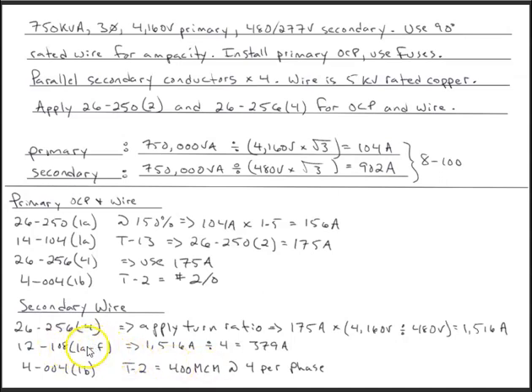So I just want to make note here, when we look at paralleling conductors, there are different ways to apply the parallels, but the way I've set them up in these calculations is we calculate for the current, apply the parallel, and then we come into sizing the conductor. So it's important, this is where I get problems with students in this section here, is applying 12108. Where do we apply the parallel? And basically in these calculations and previous calculations, we always apply the parallel before sizing the conductor. So that's just the way these exercises have been designed, and so that's what you're looking for.